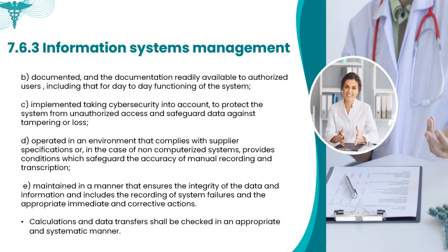Documented, with documentation readily available to authorized users. Documentation shall include information necessary for the day-to-day functioning of the system. Implemented with cybersecurity safeguards to protect against unauthorized access, tampering, and data loss. Operated in compliance with supplier specifications. For non-computerized systems, operation shall ensure that the accuracy of manual recording and transcription is safeguarded. Maintained to preserve the integrity of data and information, including recording of system failures, implementation of appropriate immediate and corrective actions, systematic and appropriate checks of calculations and data transfers.